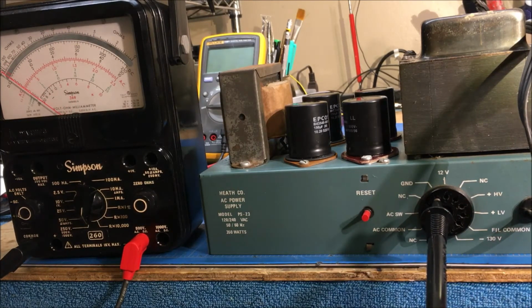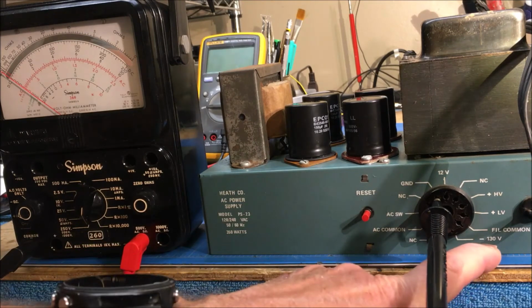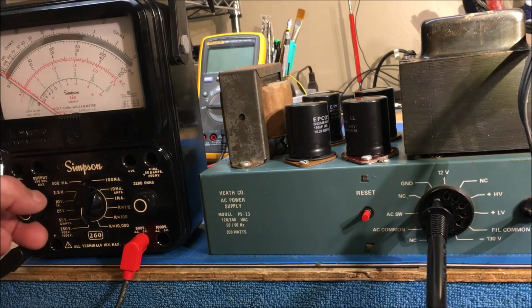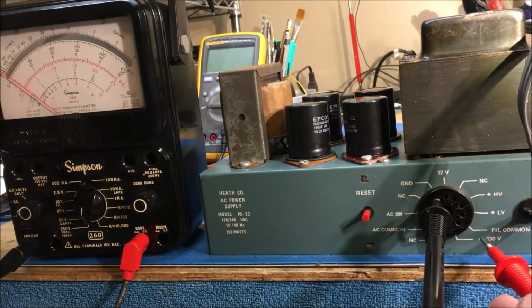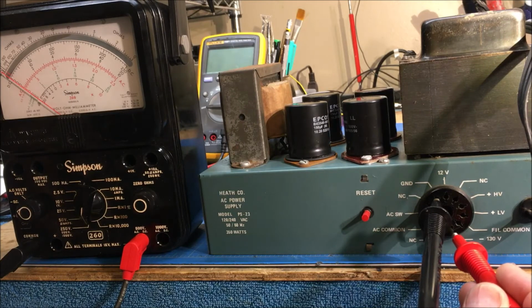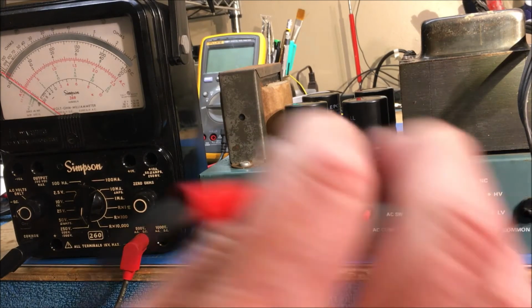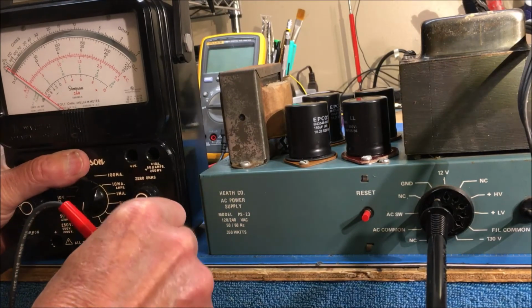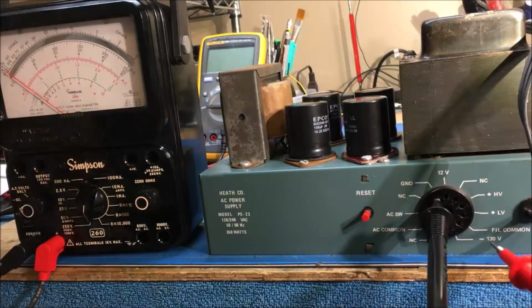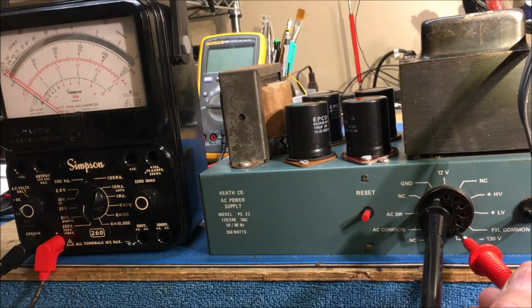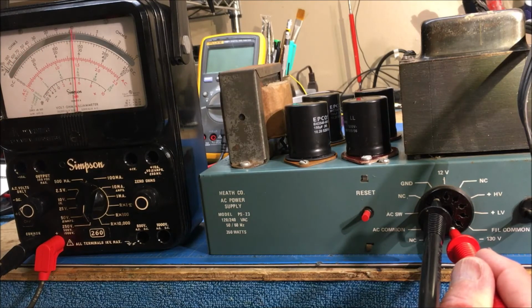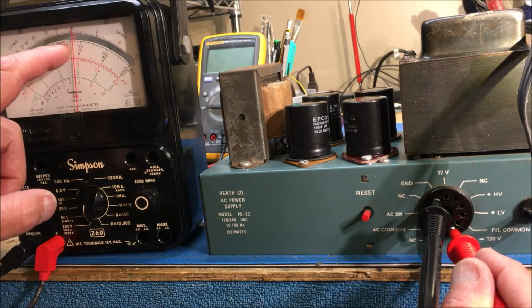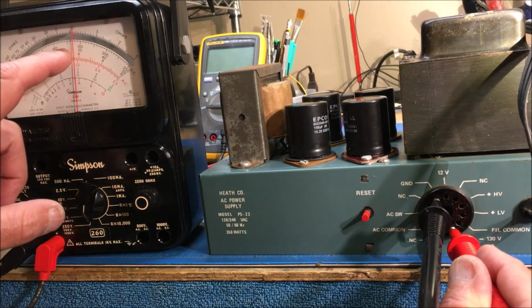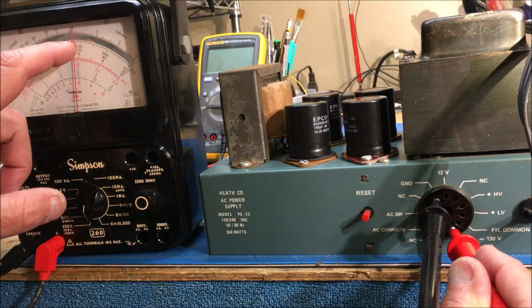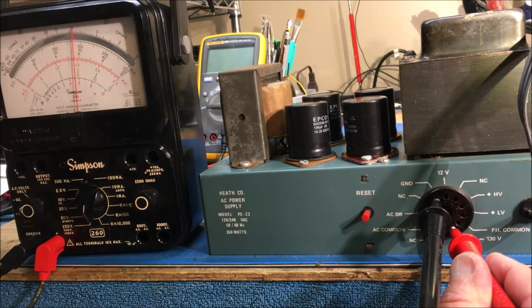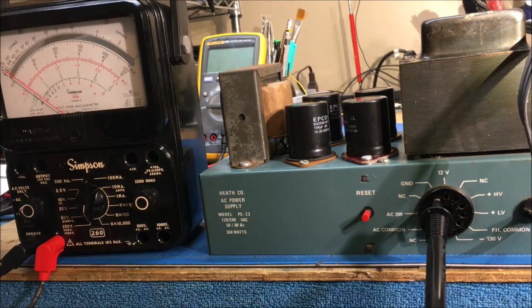Now we've got a negative 130 bias voltage, which should be at this pin right here. So we're going to switch the DC to negative, and then we're just going to check it there, and we should have, let's go to the 250. I think right here is 250 volts, so we'll go right here, and that should be the top scale, 250. And so we're looking at, there's 100, 150, now there's 150, so there's 125, so it's about 140 volts negative. So I think we're good on our power supply.